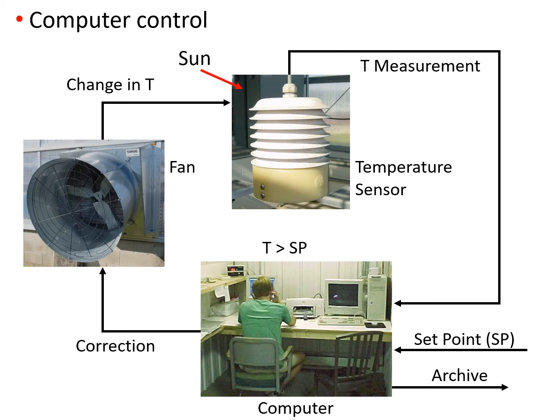Since the algorithm detects that the current temperature is above the set point temperature, it sends a signal to turn on the ventilation fans. As soon as the greenhouse temperature drops to the desired set point, the computer algorithm will turn the fans off. This process repeats itself many times a day and can incorporate additional information such as plant and weather status to make sure the plants get the best growing environment at the lowest possible cost. Note that the computer control system also archives sensor data and control decisions, making it a powerful resource for troubleshooting and for comparisons using archived data.